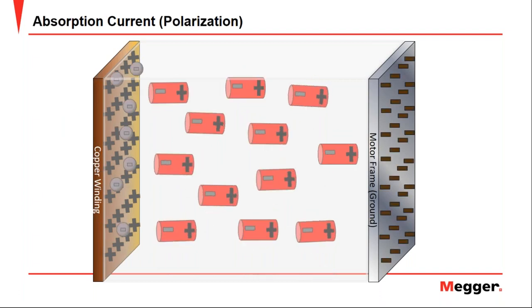Then we see here in the presentation how, in the presence of DC voltage, the dipoles present in the insulation begin to align themselves little by little thanks to the new electric field. This dipole behavior is defined as absorption current or polarization current. This current also has a high value at the beginning, but not as high as the capacitive current. It also discharges but takes longer than the capacitive current to do it.